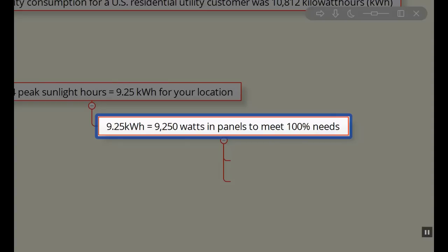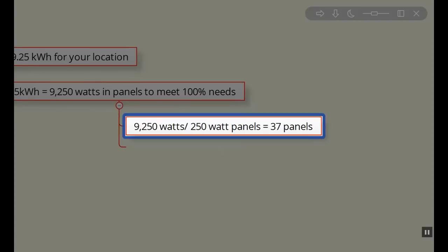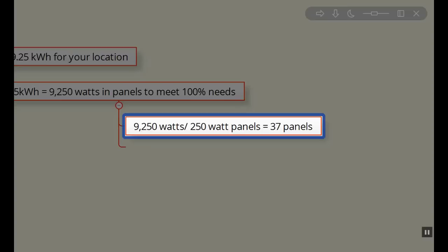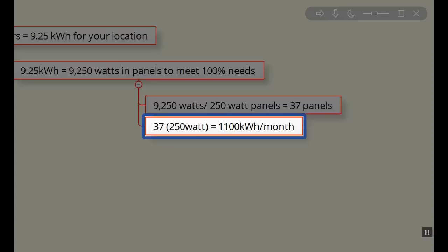Now you may decide I only want to meet 60% of my needs, or I want to meet 120%. You determine what percentage you actually want to meet. In this example, we got 9,250 watts in total panels. Now we can go ahead and divide that by 250 watt panels and come up with 37 panels we need. Now again, this is a very large system, larger than the average U.S. resident. That tells you you need 37, 250 watt panels to meet your requirements to meet a hundred percent of your needs annually. During the winter months, you won't meet that completely, but during the summer months, you'll produce more than what you need.